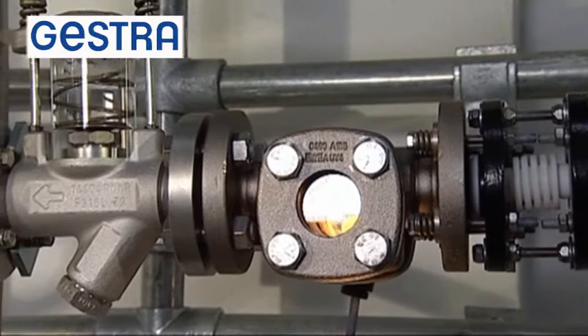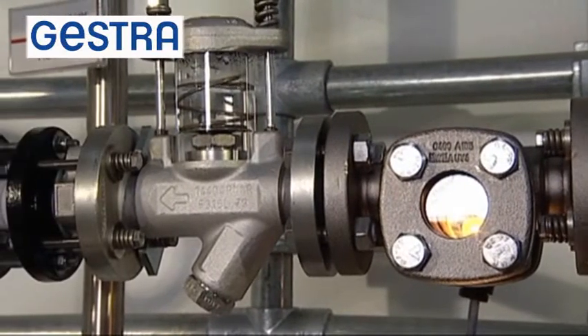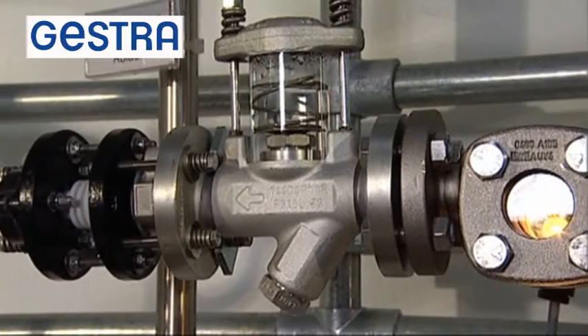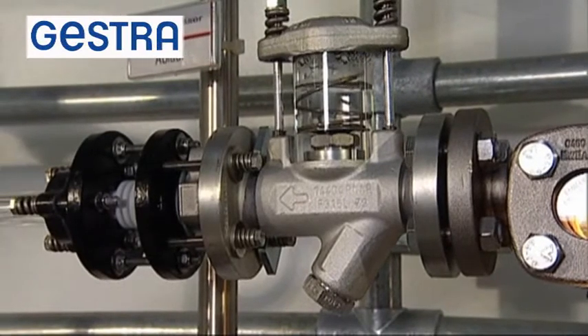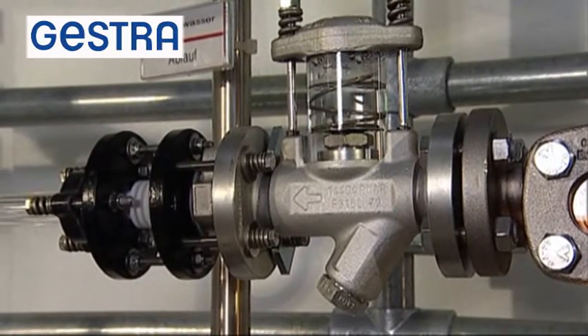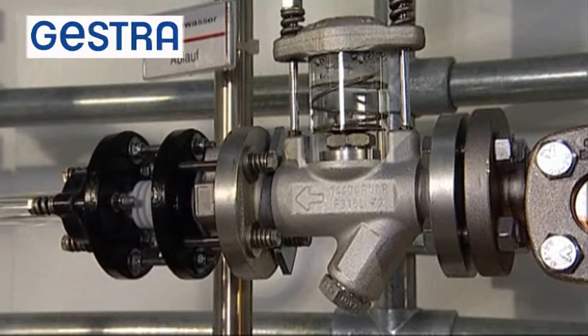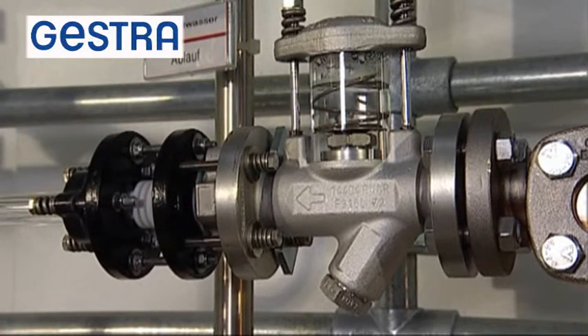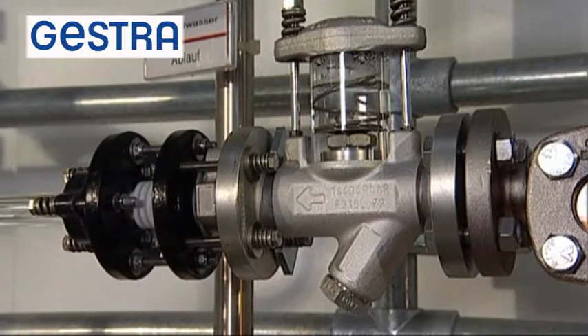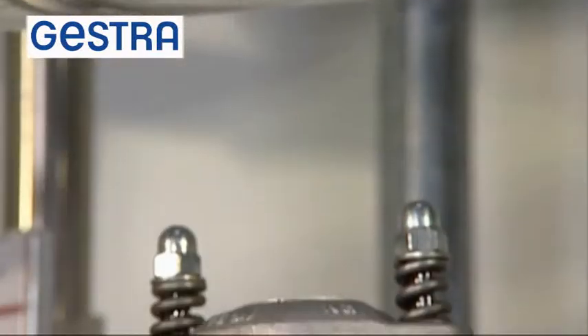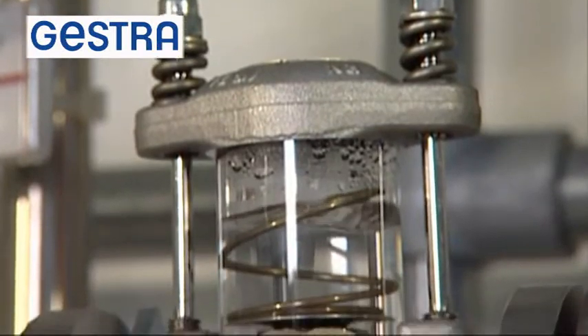Membrane steam traps offer special benefits for use in steam systems. They have a very compact design and are also available with mini bodies. They can be installed in any position. Because of the greatly reduced undercooling, membrane steam traps offer very high precision of control. Large quantities of condensate are already discharged at low pressure differentials.